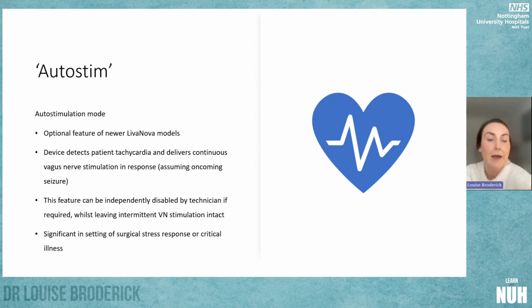Auto-stim mode, or auto-stimulation, is another optional feature of some of the newer LivaNova models. Effectively, it is a feature whereby the device picks up patient tachycardia, a preset parameter of tachycardia which it assumes indicates an oncoming seizure, and it will deliver continuous vagus nerve stimulation in response. Some patients will have the option on their device and won't have it activated, as it can be disabled independent of the regular intermittent vagus nerve stimulation.